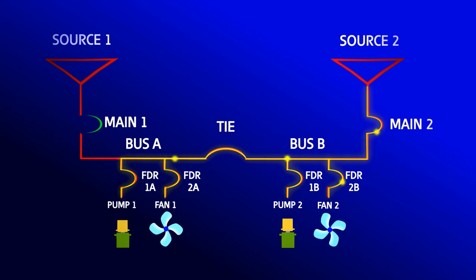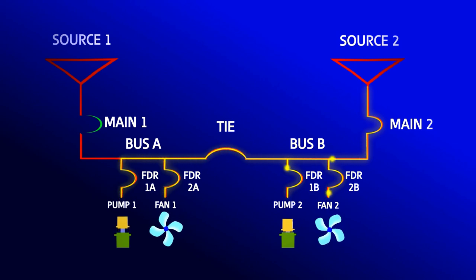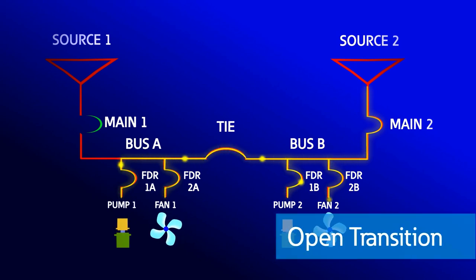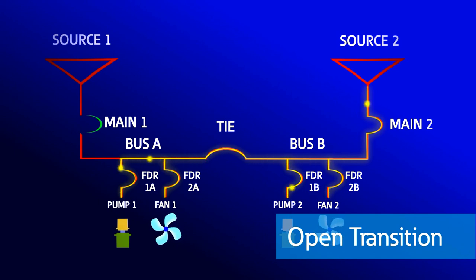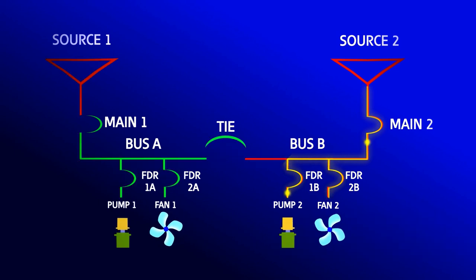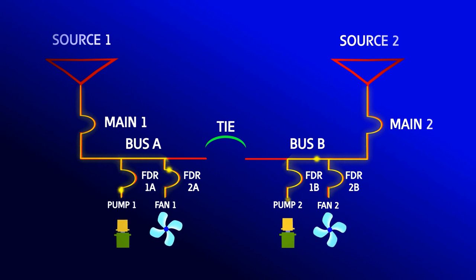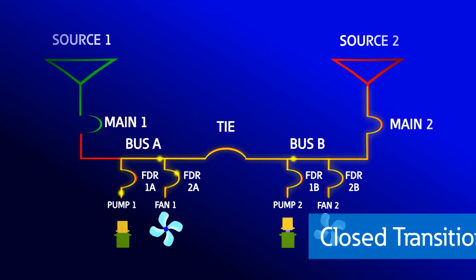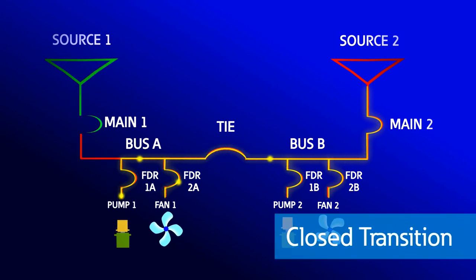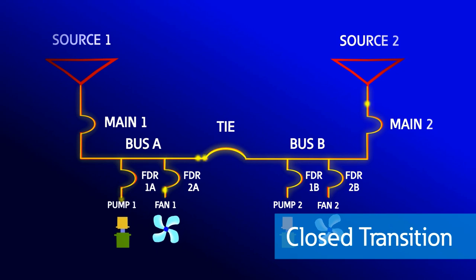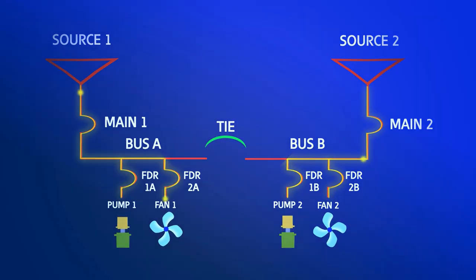When the lost source returns, there are two options to return back to normal. If your system is set up for an open transition, the tiebreaker will open prior to the lost source being connected, causing a momentary disruption to half of the loads. With a closed transition, the sources are paralleled prior to the tiebreaker opening and the loads are maintained.